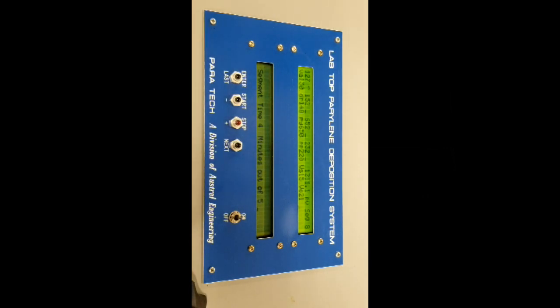You see the vacuum pressure is now reading around 1100, 1200 microns. And we're 4 minutes into the 5 minutes of the segment. So once it finishes the 5th segment, times out, and the vacuum gets below 21, the recipe will end, and at that time the vaporizer and the door will begin to cool.